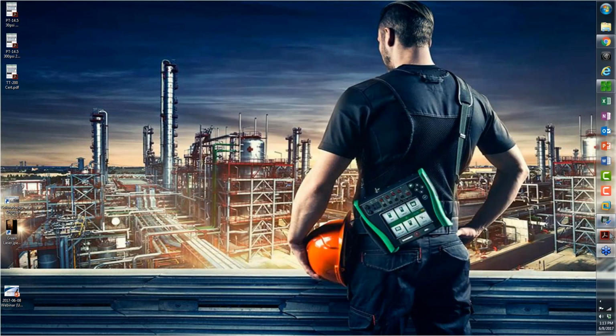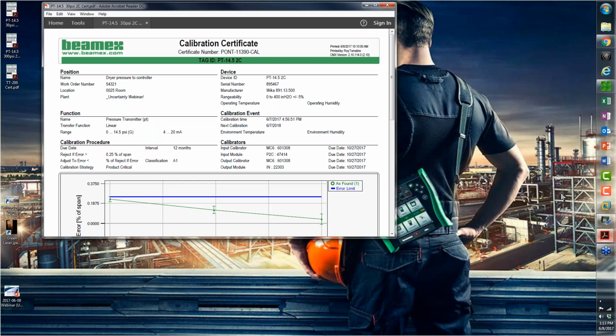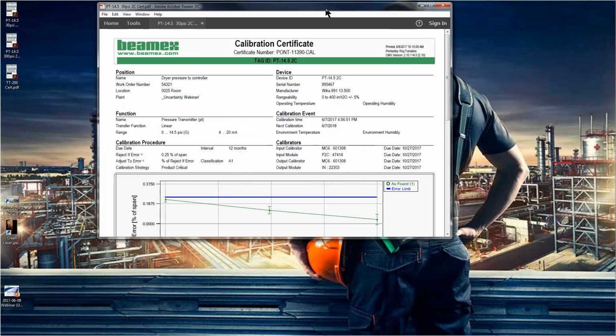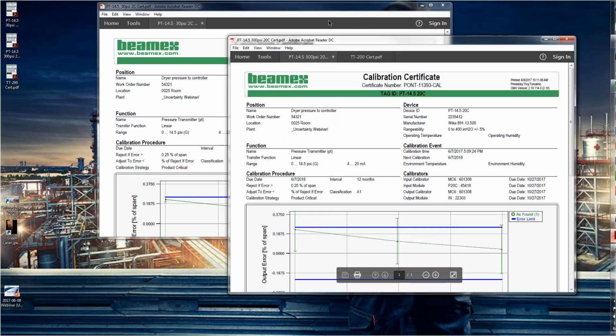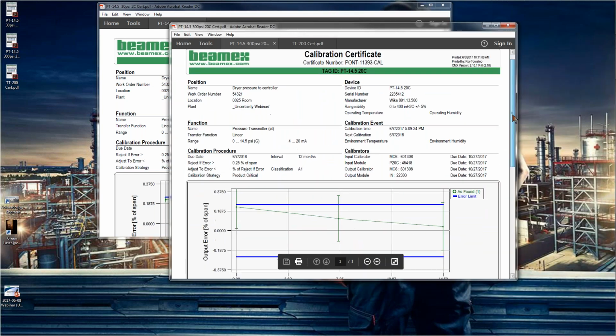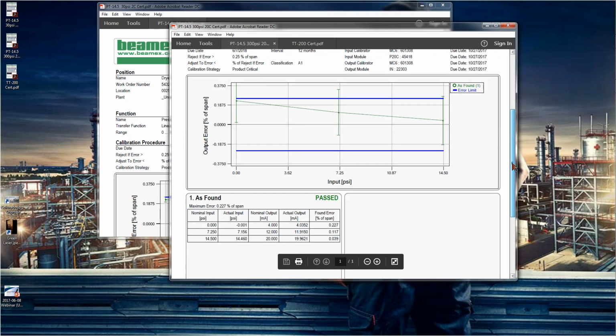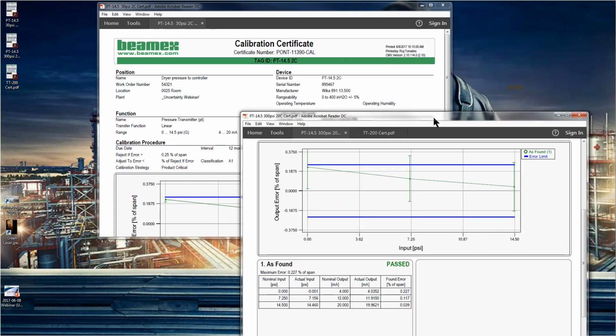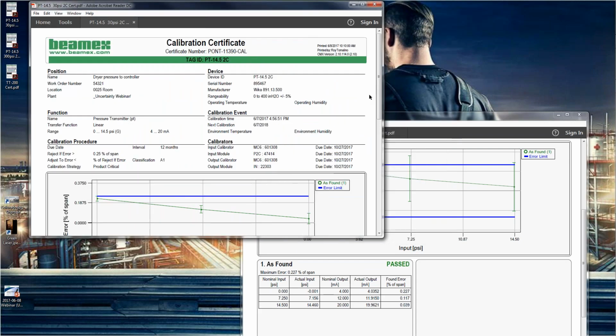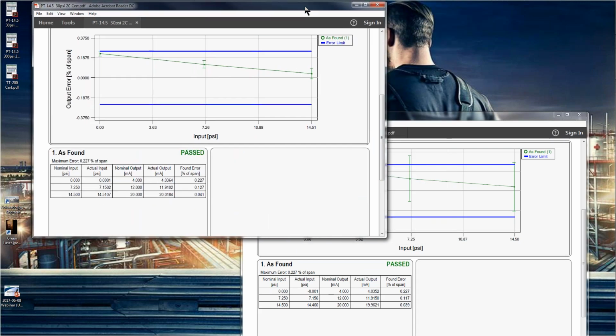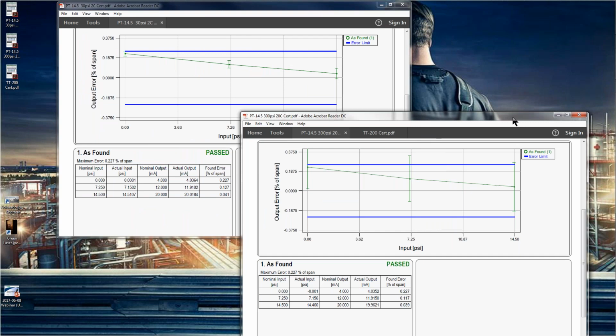Now, I promised you a PDF. Let me show you that. So here's my calibration certificate for my 30 PSI, and let me click on the 300 PSI. Here's my calibration certificate. I'll scroll down so I'm just looking at the graph itself. And here's the graph on the 30 PSI. So now you should be able to see both of them, and you should be able to see those guard bands. Is this coming through okay, Sarah, Ned? Looks good, thank you. Good.